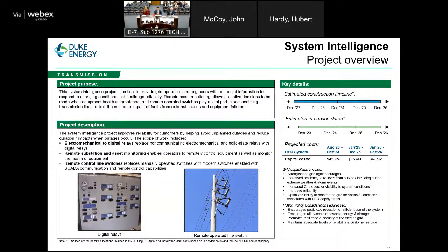Now, the other area I'll mention for system intelligence, you can see in the center bullet, is our remote substation and asset monitoring. Remote substation monitoring is essentially traditional SCADA improvements where we have the supervisory control and data acquisition. But the asset health monitoring is a relatively new project for us. And what we're doing is deploying monitors we call condition-based monitors. These are primarily on our substation transformers. And these monitors go on that transformer and they analyze the oil and other characteristics in that power transformer to determine, do I see signs of a problem?